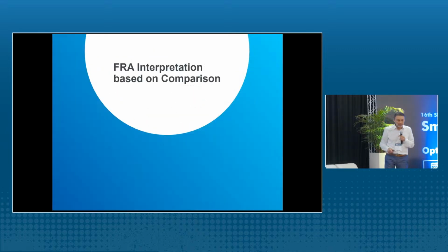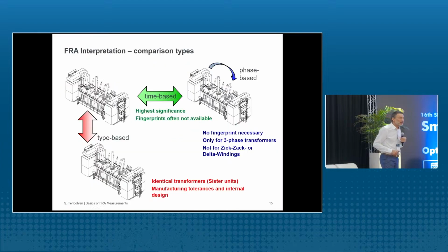This I will skip. And now we come to the tricky point. How should we interpret the FRA? I said before, you need somehow a fingerprint. So this is a time-based comparison. You have a transformer. You measure the FRA at this transformer after the factory acceptance test, and then some years later you repeat the measurement, same phases, same transformer, with the same setup, and then you can say, if this frequency now changed, we have a problem.